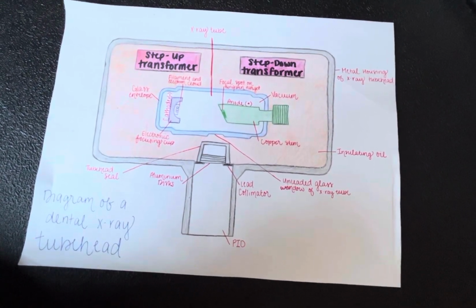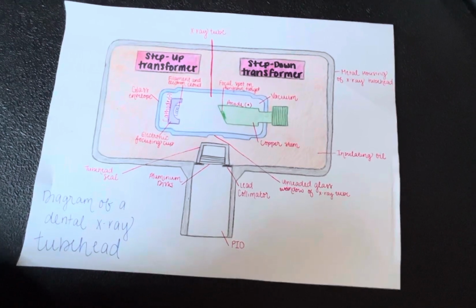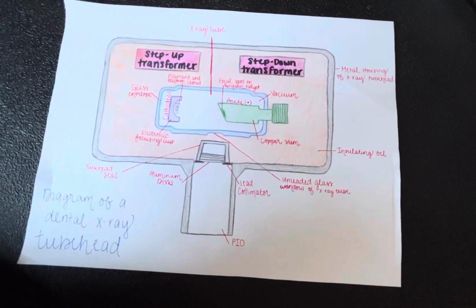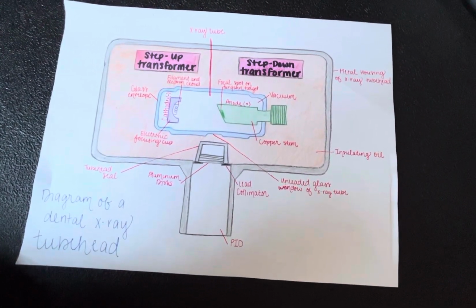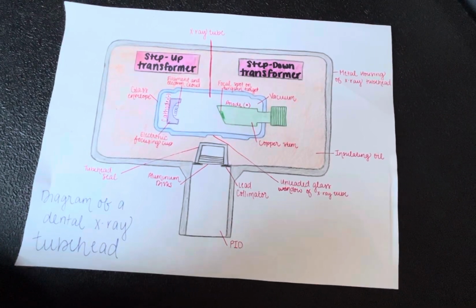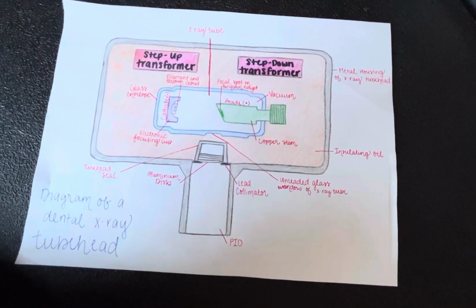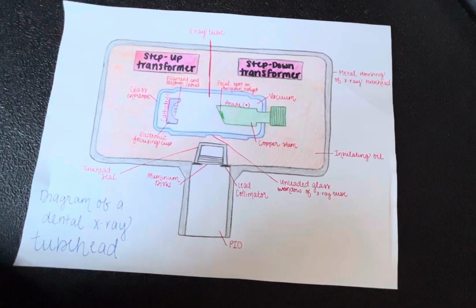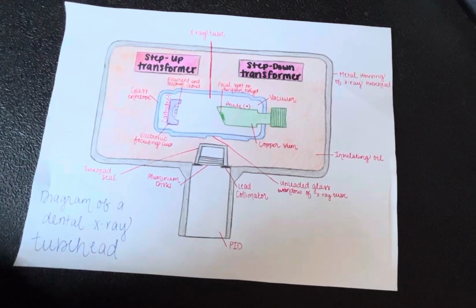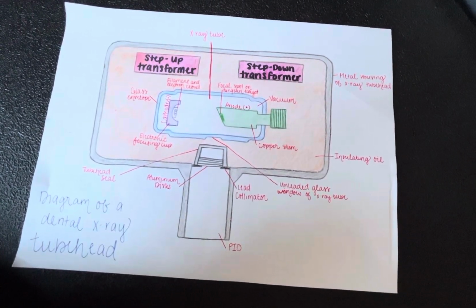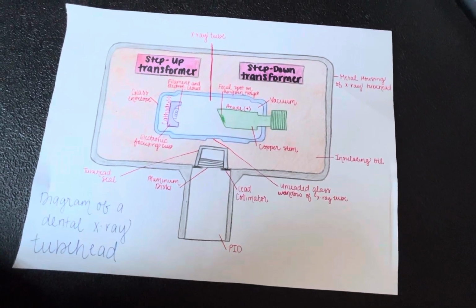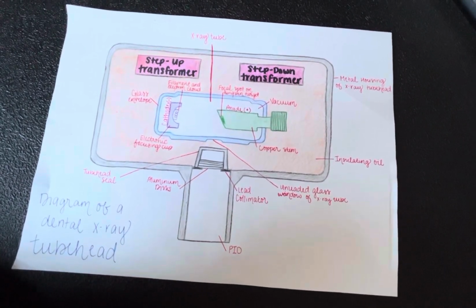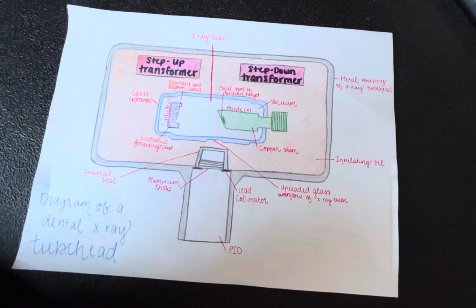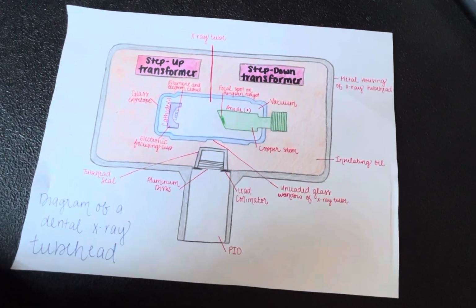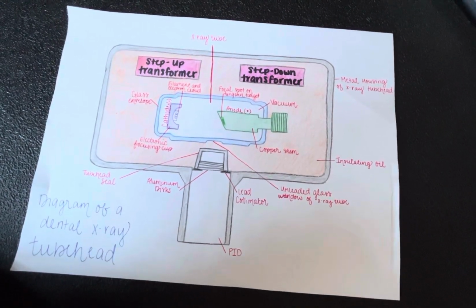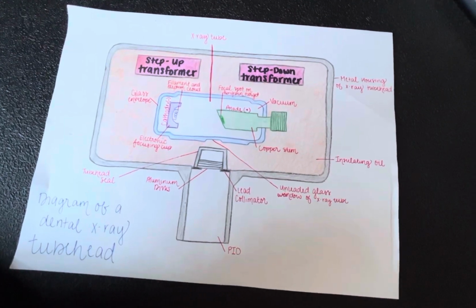2 electrical circuits are used in the production of X-rays, a low voltage and high voltage. The low voltage is also called the filament circuit, and it uses 3 to 5 volts. It regulates the flow of electrons to the filament in the cathode of the X-ray tube and is controlled by milliamperage. The high voltage circuit uses 65,000 to 100,000 volts and provides the high voltage needed to turn the electrons into X-rays. It's controlled by kV.